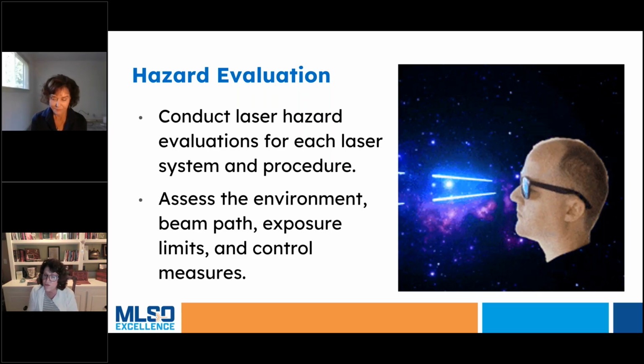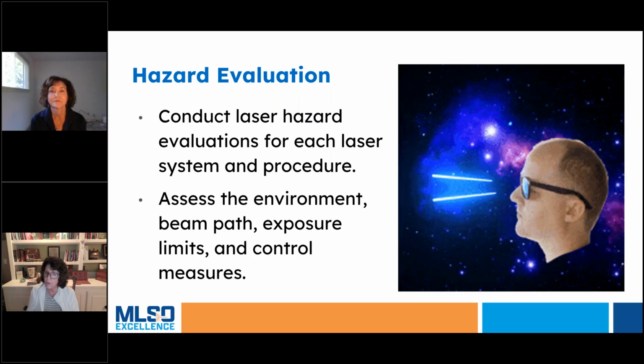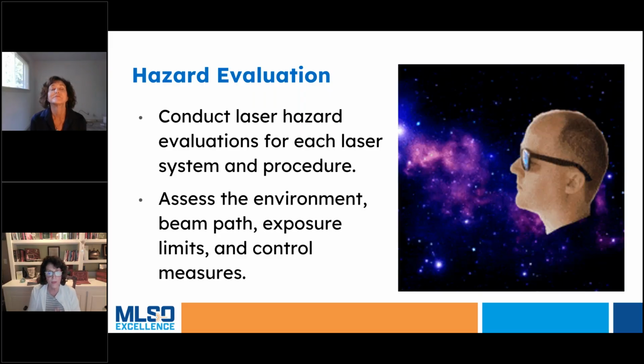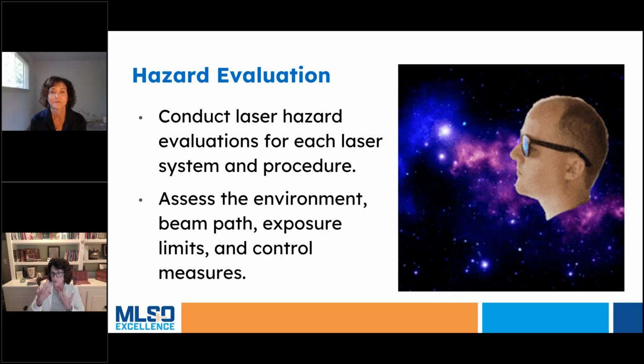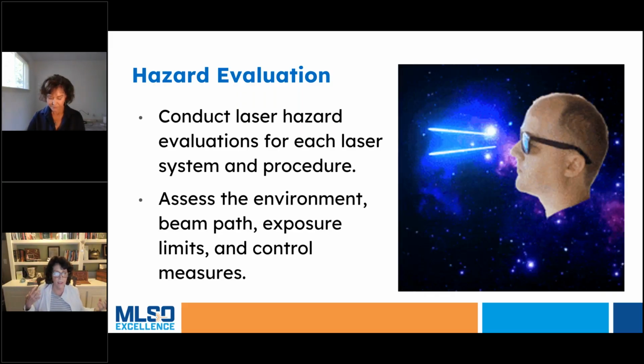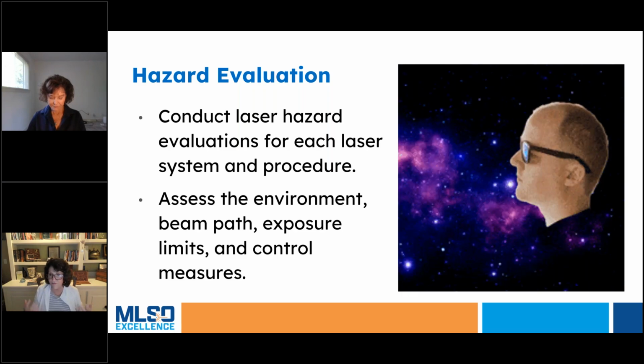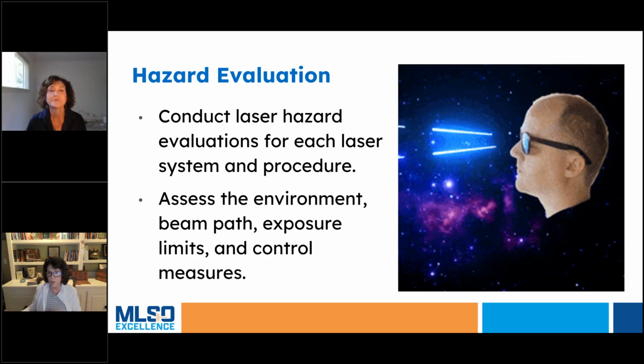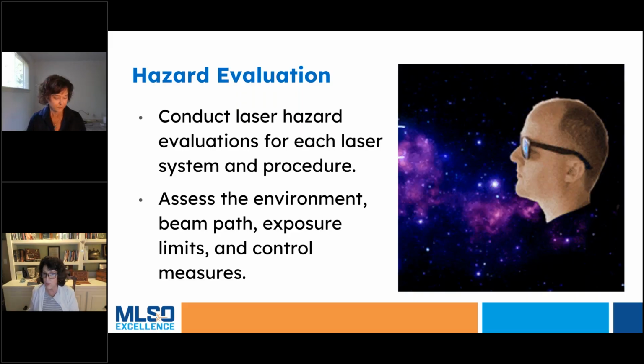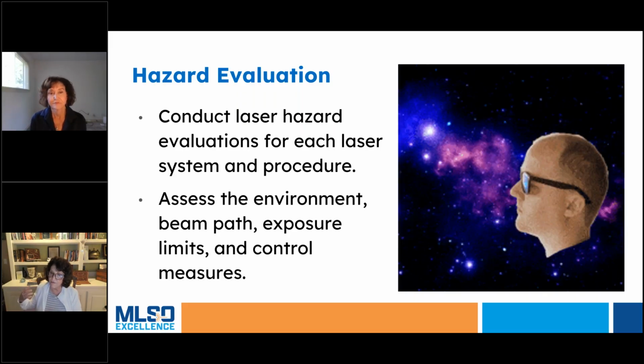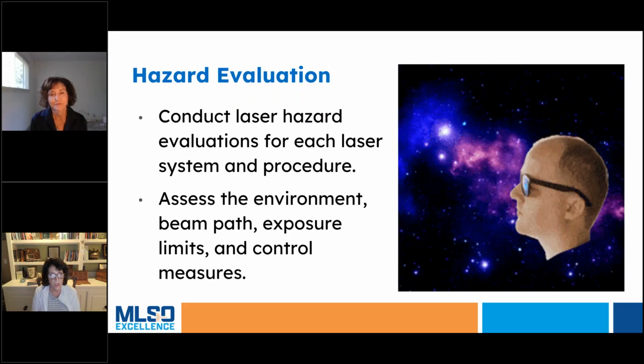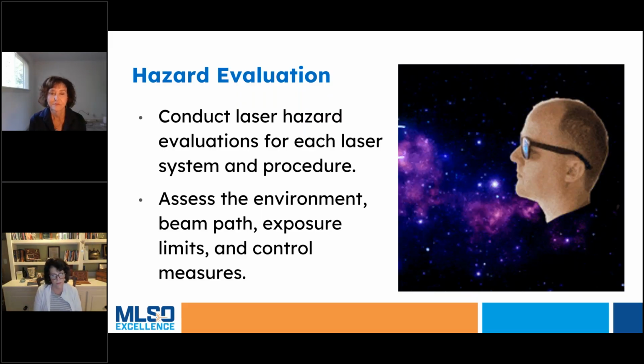Hazard evaluation is very different for airway protocol than it may be for urology, because you've got endotracheal tubes that have to be specialized. You have anesthesia gas mixtures, which could be highly flammable, very different than when you're working in a lower tract environment using a different kind of laser and a very different type of delivery system. So that is a type of hazard evaluation.